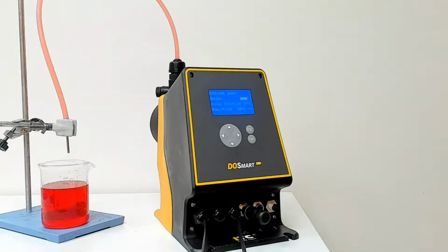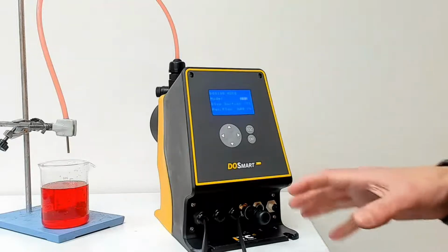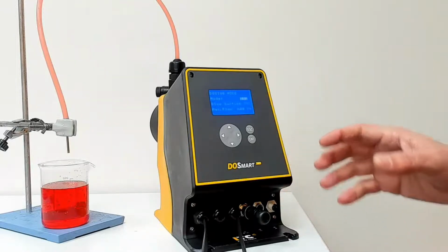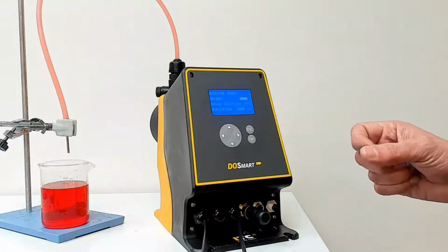As we consider it very important to ensure that the suction is done properly, we put the focus on designing dosing pumps with a high suction capacity. For this, we will show you the capacity of that pump, which can have a suction lift of 6 meters. We can't do this right now here, but we can share a video where you can see how it performs.